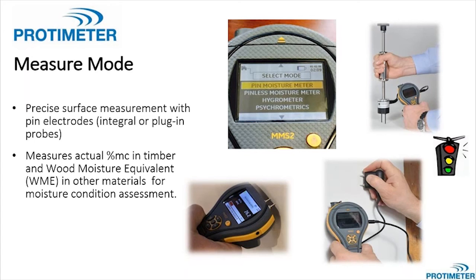You can also plug accessories into the side of the meter. That includes accessories like the popular hammer electrode that plugs into the tip of the meter, as well as our various extension leads. The hammer electrode is useful for wood. You can take moisture readings at depth and pinpoint your areas of moisture intrusion or moisture problems at depth.